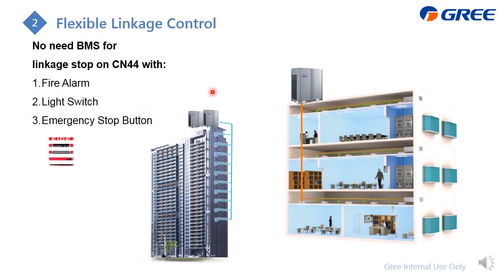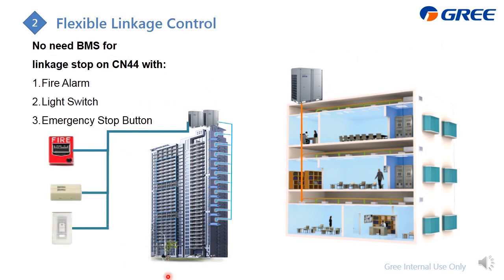Also at the outdoor unit PCB, there is a CN44 to connect with either the fire alarm or light switch or the emergency stop button. With this one, we can stop the system immediately. So an example to display this is, this is the outdoor unit, and inside this building, when it receives the fire alarm signal, which is sent from here, then it can immediately stop operating.